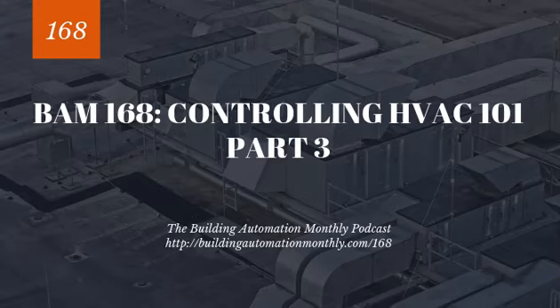Now, temperature control is typically driven, and this will be consistent for water-cooled chillers as well, off of three variables: either schedule, you're scheduling a static temperature, you're doing a load calculation in the building and doing a reset of supply temperature, or you are resetting it based on outdoor air. Yes, there are outdoor air resets for chilled water. They're not that common, but they do exist. Load is becoming a more common reset, and scheduling just, hey, it's on and it's going to run 42 all the time. That is one of the most common ways of running a chiller.